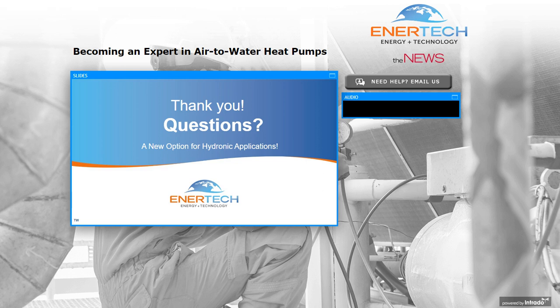Okay, great. How well does the system work for existing residential replacement remodel? It can work really well for replacement. We would have to look at the convectors, especially if we have cast iron radiators or baseboard heat or something like that. It's possible that we may not have high enough temperature with the heat pump, but it's also possible that they have upgraded their windows and insulation and so forth, and maybe we don't need as much capacity, or we could possibly add some additional radiation surface. So it generally is a really good fit.